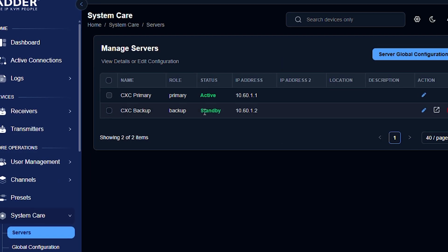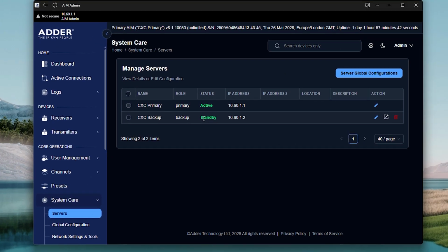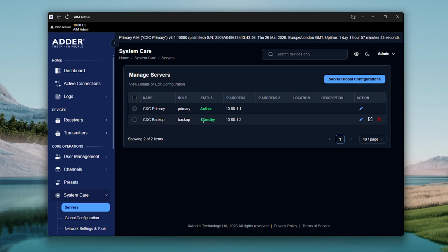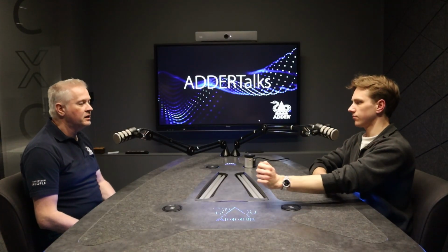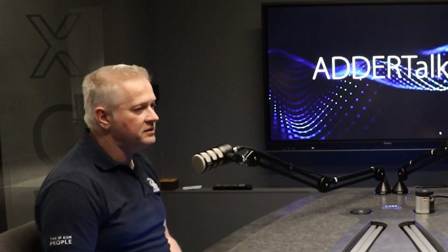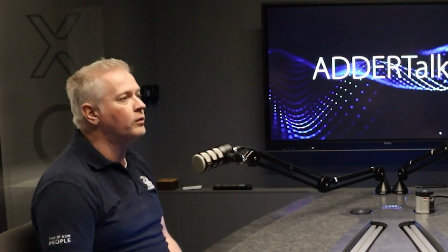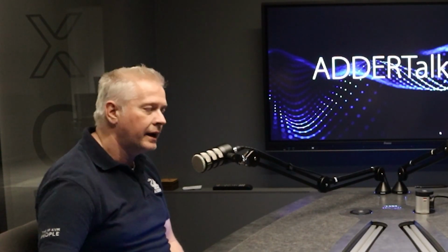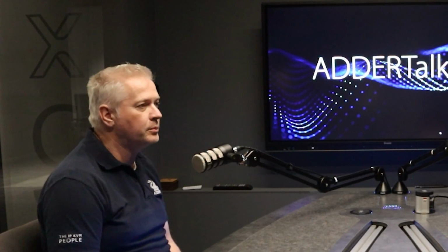Obviously, most people run multiple management servers, so you have a main or a backup. And it might be that you're in a campus and you have many outlying buildings in which you can put a satellite server in the event of communication breaking between the buildings. And it's very easy to then see the status of those and to see that they are online and their databases are backed up. So if there is an issue and it's flagged on that page, you can then go off, see what the issue is and look at rectifying it in an appropriate fashion.